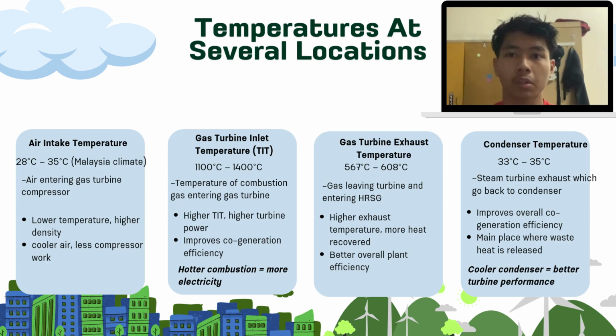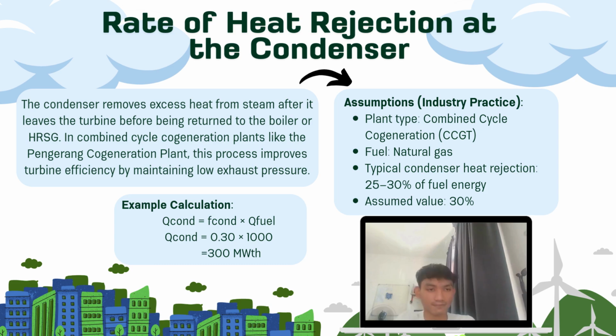efficiency. And the last one is condenser temperature, which is 33 to 35 degrees Celsius. Condenser temperature is the temperature of the steam turbine exhaust going back to the condenser. It improves overall cogeneration efficiency, and it is the main place where waste heat is released.